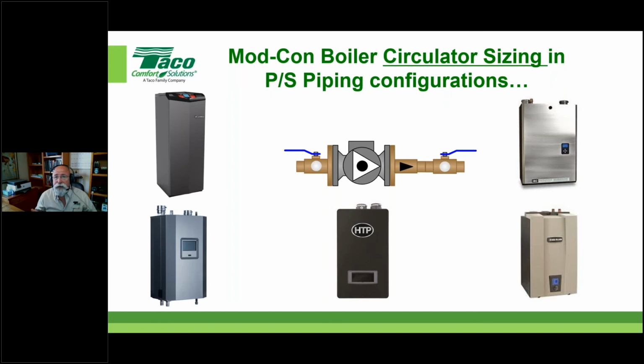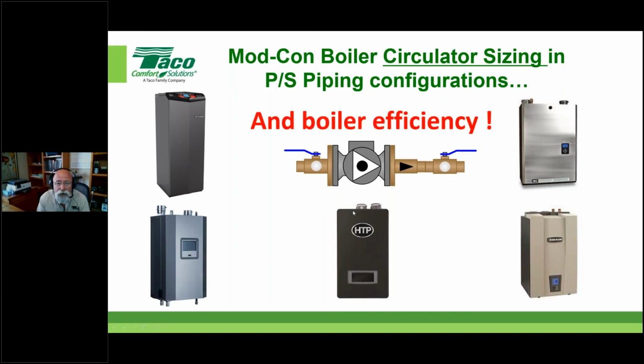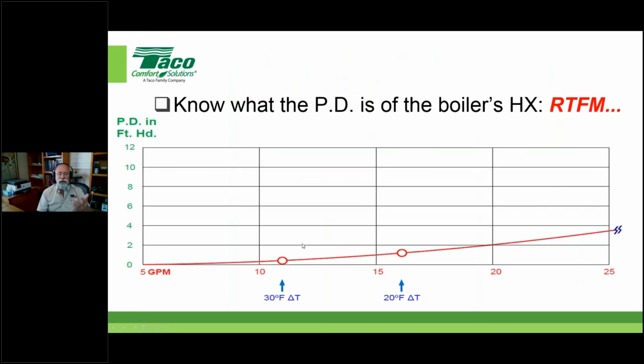They think just filling up the system, they think, like in our case, the 4900 does all the work for you. No, it doesn't. You have to do the initial purge correctly. So anyway, this slide is focusing on the sizing of this near boiler pump in a primary secondary configuration and how that helps us in the overall boiler efficiency.